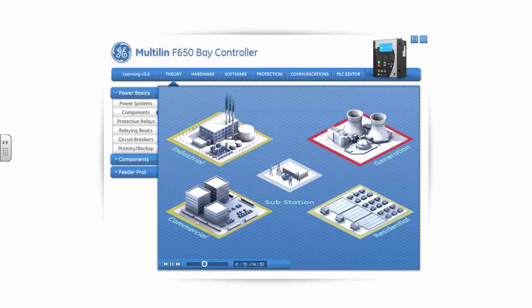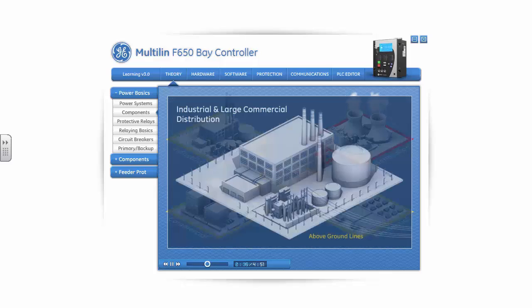The three-phase power travels from the generating station over high power lines to substations. Different voltages are required for residential, commercial, and industrial customers. And so, at substations, breakers and transformers route and step down the voltage to a suitable level for distribution. From the substation, the industrial or commercial power lines take the power above or below ground to a large transformer which steps the three-phase voltage down to a suitable level for the plant or building.